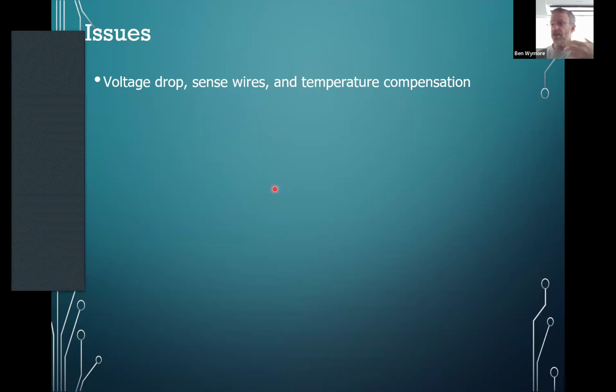It would tell the controller that the temperature has dropped enough that it should raise the voltage it's pushing by 30 millivolts per degree Celsius. So if I imaginarily raise it by 10 degrees, the controller thinks the temperature decreased by 10 degrees and compensates by 30 millivolts times 10, which is 300 millivolts, or 0.3 volts. Now the solar controller is pushing 0.3 volts more than it's supposed to, but at that level of current, that 0.3 volts will disappear in voltage drop, so the voltage at the battery will be correct.